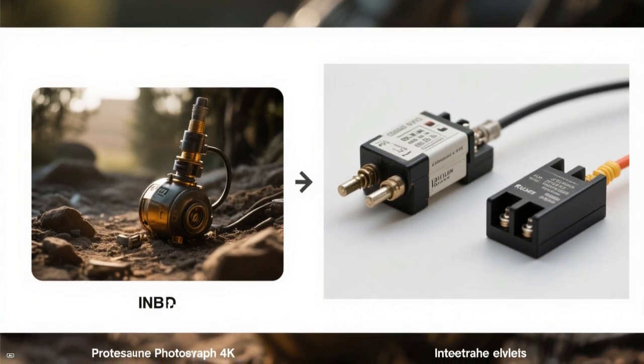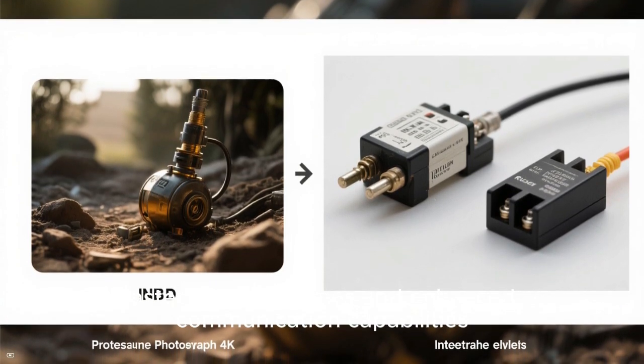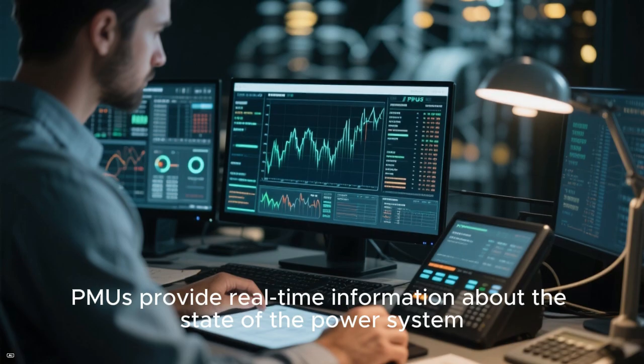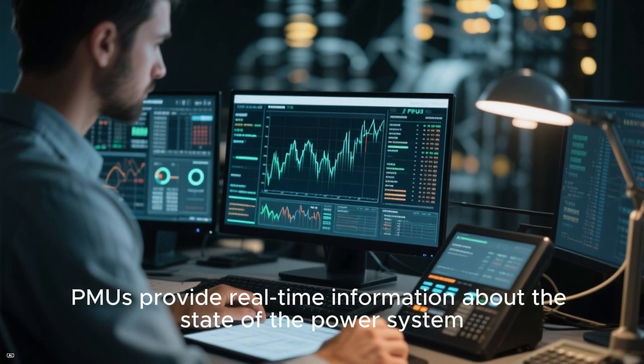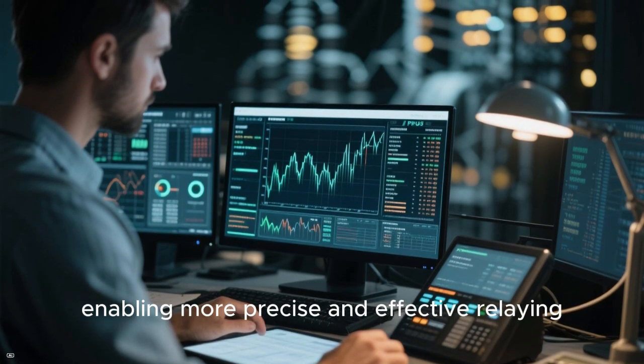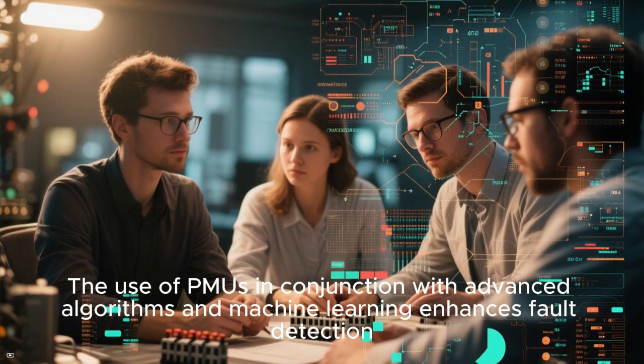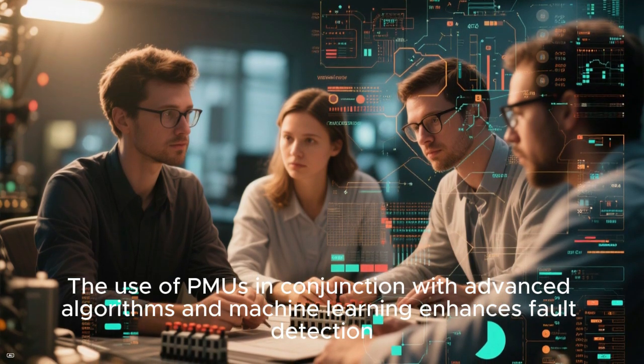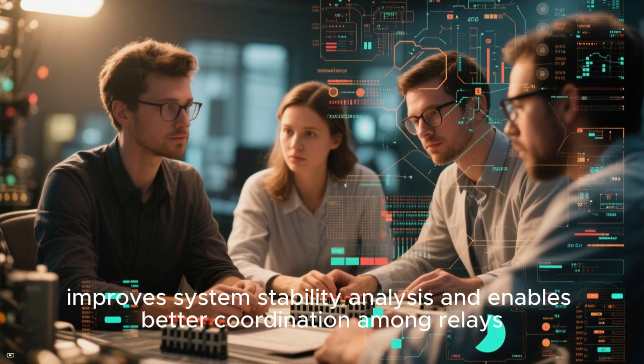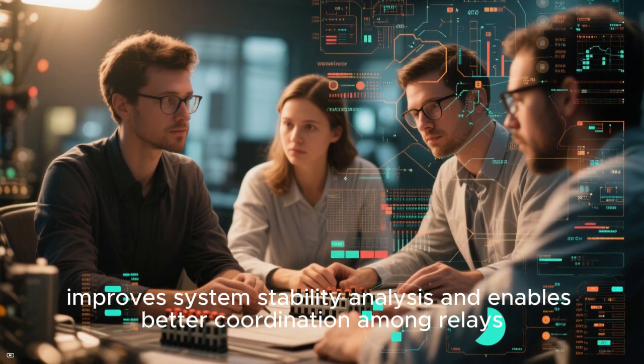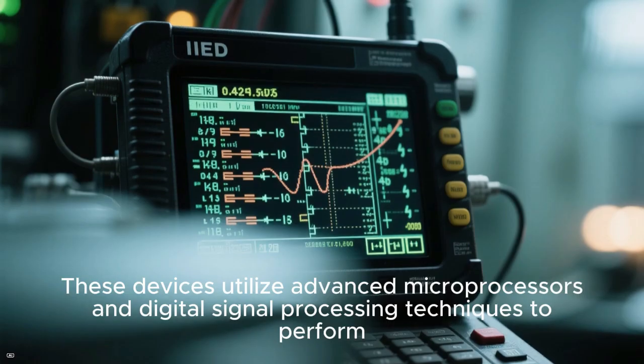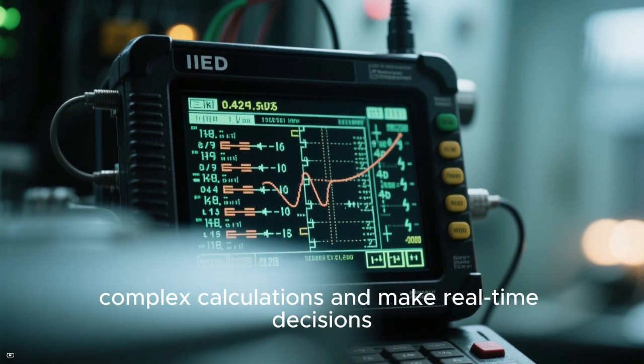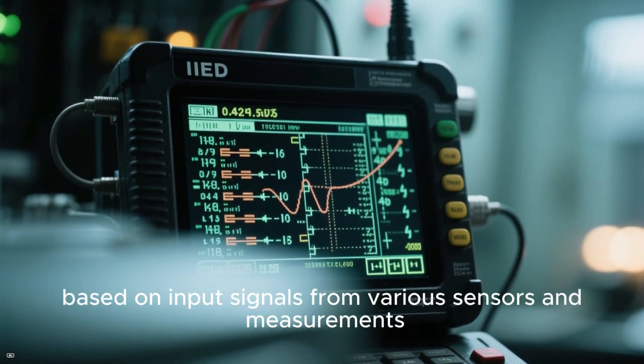IEDs offer several advantages over conventional relays, including improved accuracy, faster response times, and enhanced communication capabilities. PMUs provide real-time information about the state of the power system, enabling more precise and effective relaying. The use of PMUs in conjunction with advanced algorithms and machine learning enhances fault detection, improves system stability analysis, and enables better coordination among relays. These devices utilize advanced microprocessors and digital signal processing techniques to perform complex calculations and make real-time decisions based on input signals from various sensors and measurements.